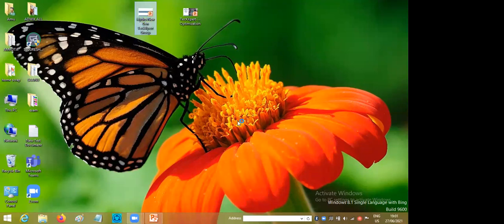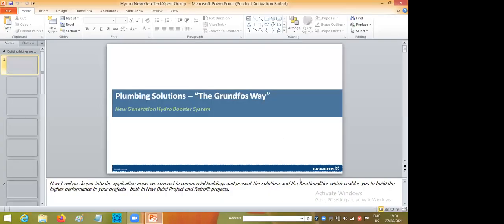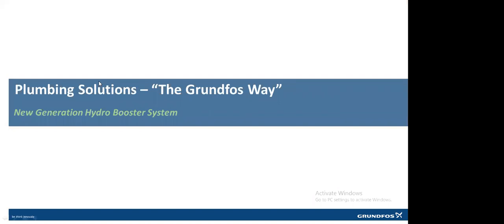There is one question from Mr. Sharanam Baswa. We have a 55-meter building height with hydro-pneumatic Grundfos pumps, 3 into 15 kilowatt, installed at basement 2. Above the 8th floor, we are not getting 6 kg pressure, with the design set point of 6 kg at the PLC. What can be the reason that you are not able to achieve the required pressure?